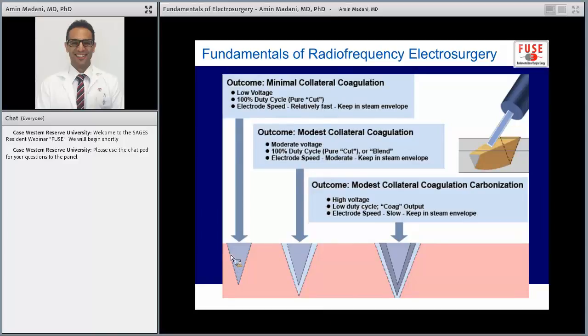Here on the left, I have a diagram where here is the tissue. And I'm just going to get a pen here to show you. So you touch the electrode, you're touching this area here. You're going to raise the cellular temperature to above 100 degrees Celsius, and it's going to vaporize the tissue, and you get a cutting effect. But because it's low voltage, it's lower energy, and this surrounding tissue does not experience a high rise in temperature. So you don't desiccate this tissue very much. It still stays healthy.